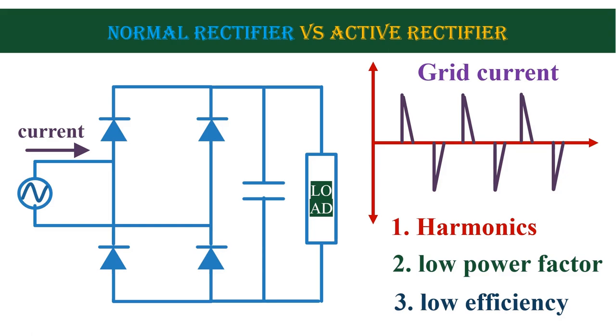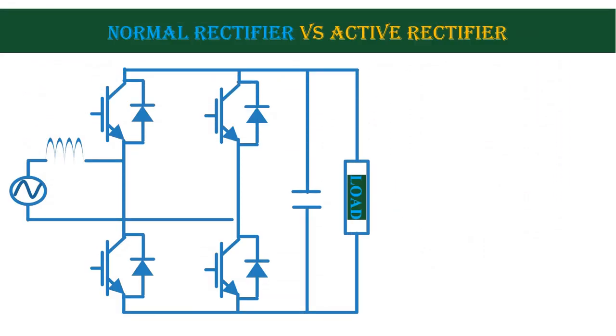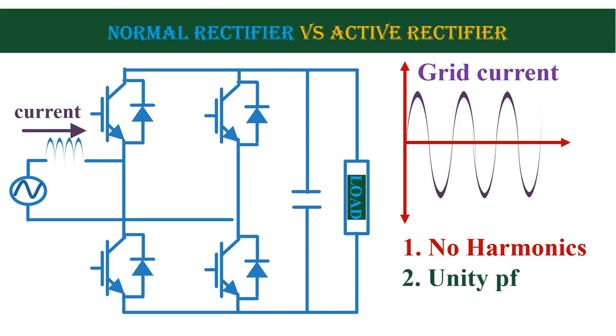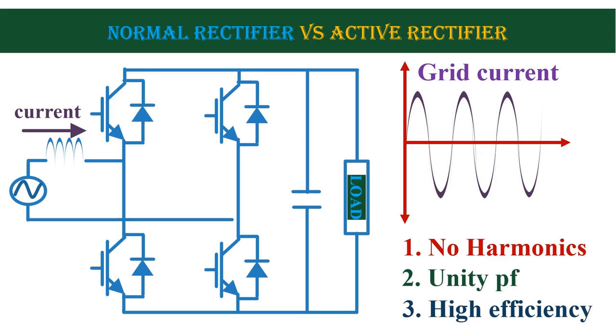To avoid all these issues, we use an active rectifier. Instead of diodes, here we use MOSFET or IGBT. We also use an inductor which is connected in series with the grid. The major advantage of this circuit is that the current drawn from the grid is pure sinusoidal, so there are no harmonics generated by this circuit. Also, we can achieve unity power factor. Since the voltage drop across the MOSFET is less compared to the diode, the losses are minimum, so we can get higher efficiency.